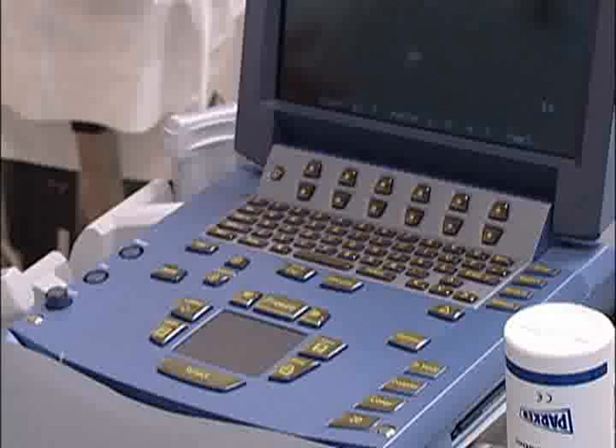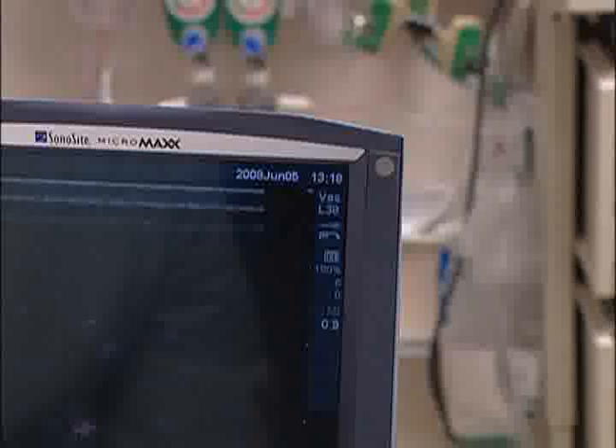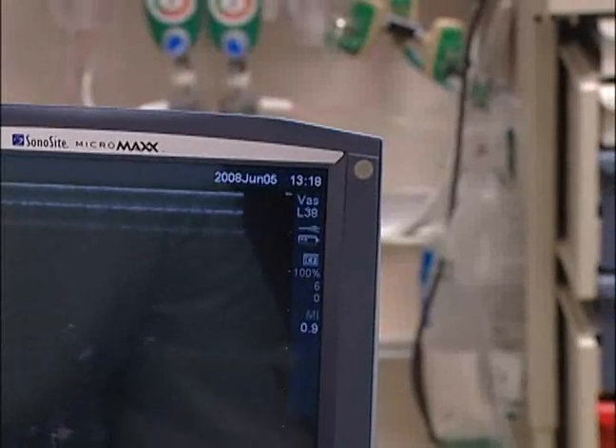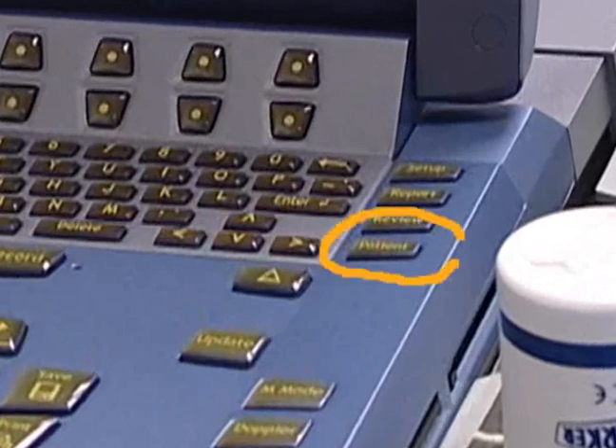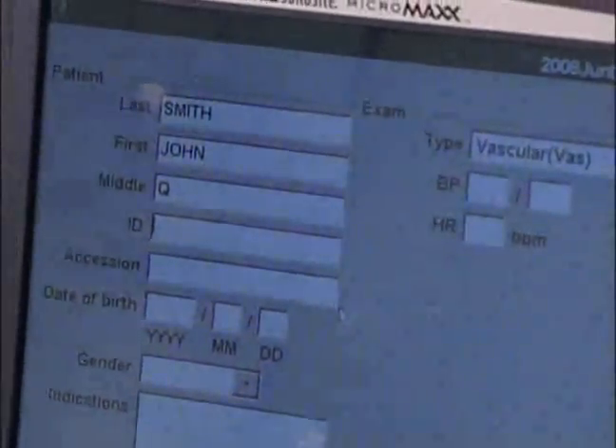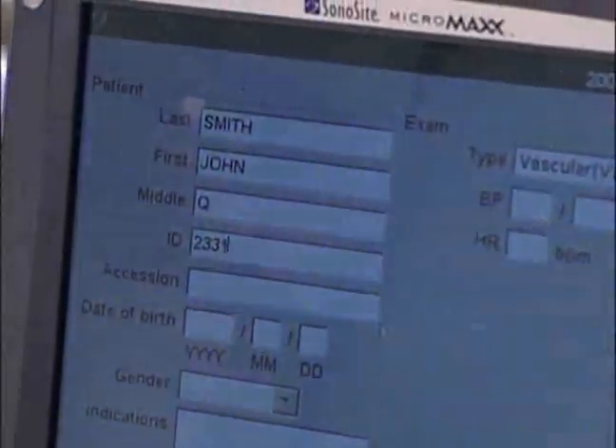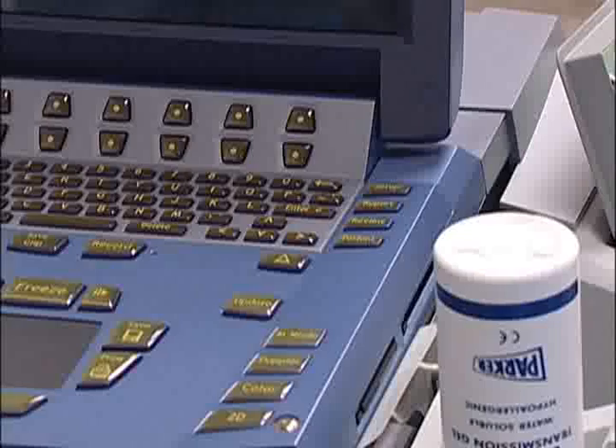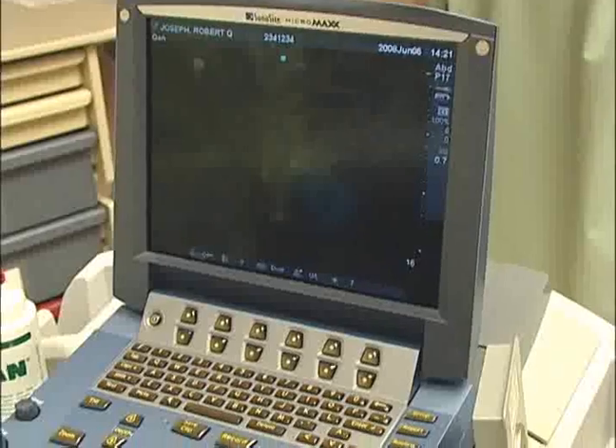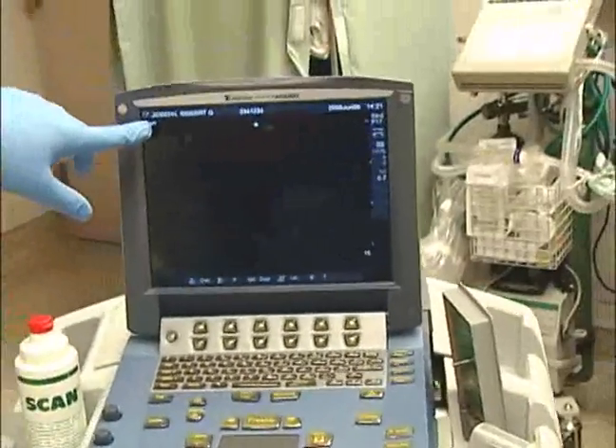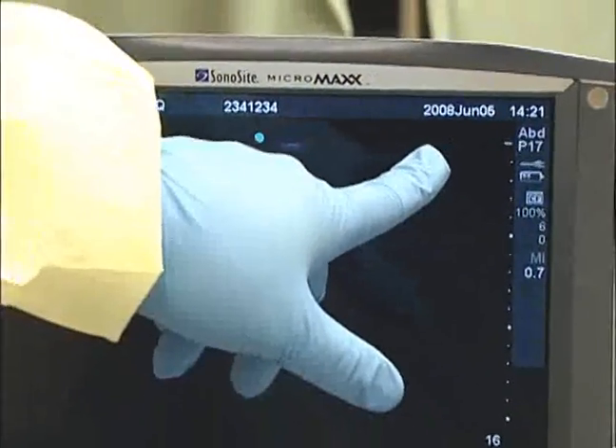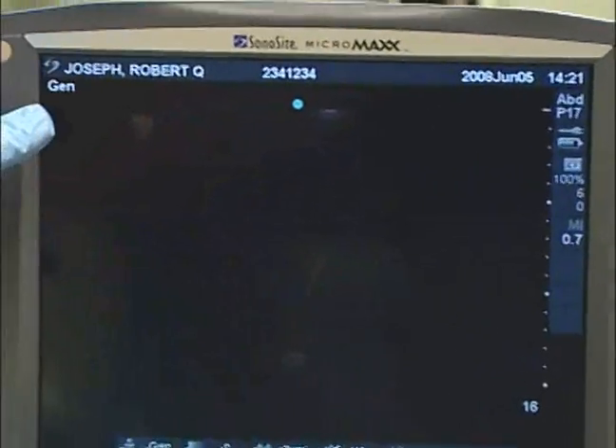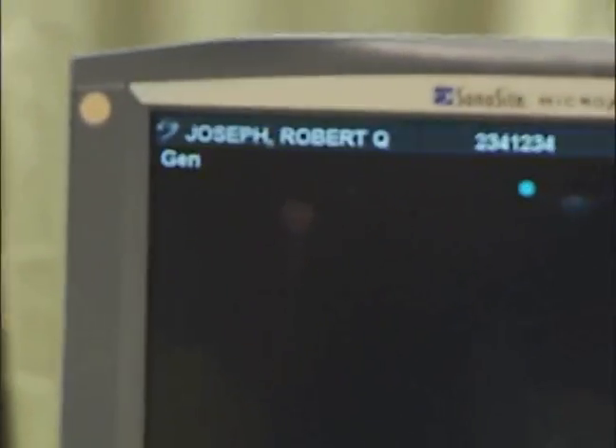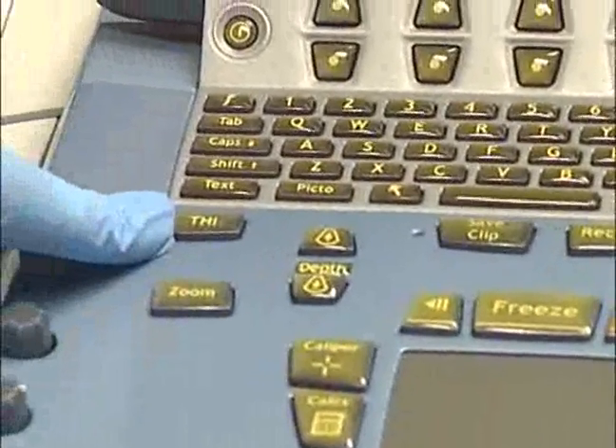After turning on the machine, make sure that the correct date and time are shown on the machine. The patient's name should be entered by pressing the patient button. Enter the patient's name and MRN. When done, hit the patient button again, or the done button. Now the patient's name is displayed on the screen. Make sure that proper time and date is indicated. Make sure that you're in general mode and that you're not in THI or any other special modes to start the ultrasound.